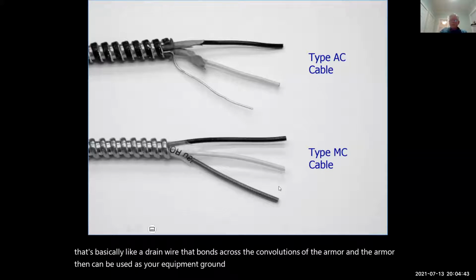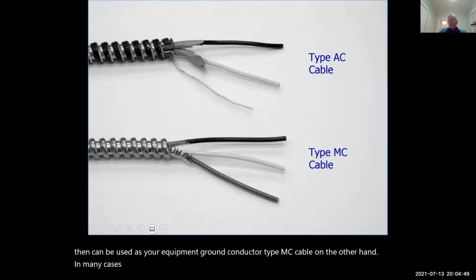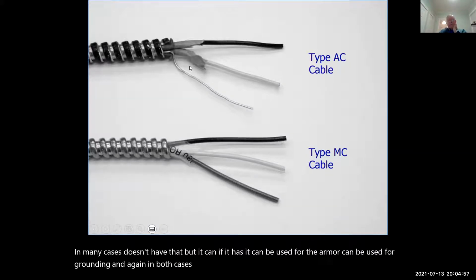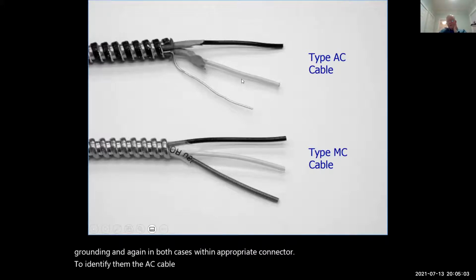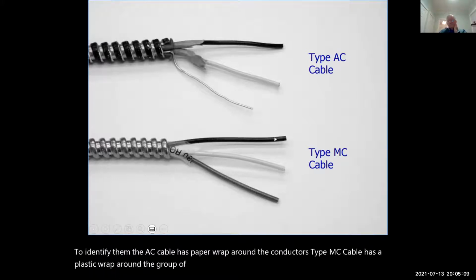Type MC cable, on the other hand, in many cases doesn't have that, but it can. If it has it, the armor can be used for grounding. And again, in both cases, with an appropriate connector. To identify them, the AC cable has paper wrap around the conductors. Type MC cable has a plastic wrap around the group of conductors.